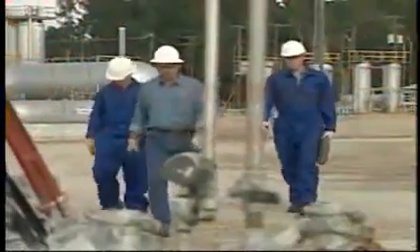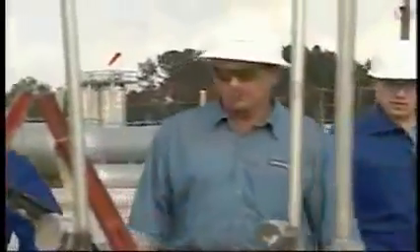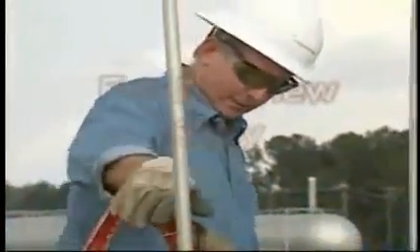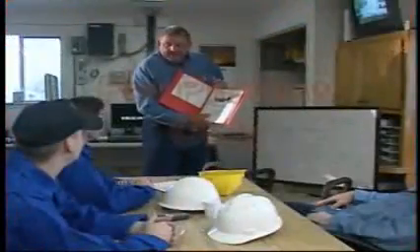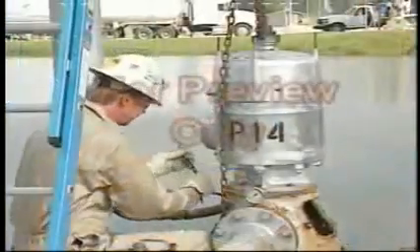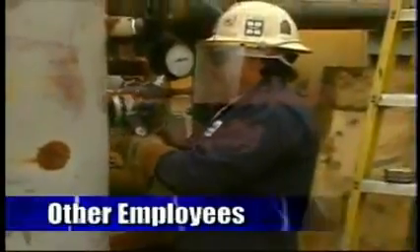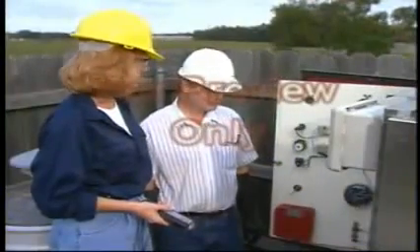An employee whose job requires him or her to operate or use a machine or equipment on which servicing or maintenance is being performed under lockout or tagout, or whose job requires him or her to work in an area in which servicing or maintenance is being performed, is called an affected employee. They must know the purpose and procedures for energy control to fully understand the importance of not using a machine that is locked out or tagged out. An affected employee becomes an authorized employee when that employee's duties include performing service or maintenance covered under this standard. Employees who work in areas where energy control procedures are used but are not part of the process are termed other employees. It is important for them to understand lockout-tagout rules, not attempt to re-energize machines that are locked out or tagged out, and to learn the limitations of the tagout devices.